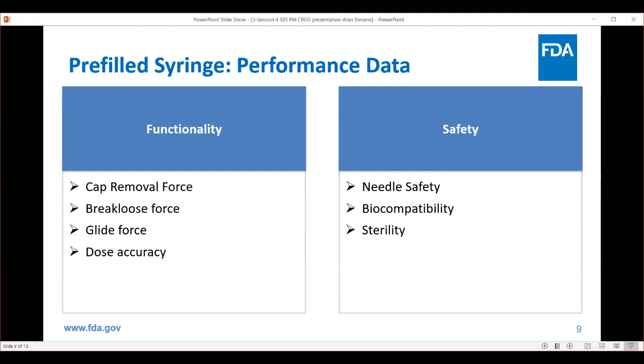So I'm just going to walk through the key performance criteria that we're looking at generally for syringes and injectors. So for functionality, we're looking for cap removal force, break loose force, glide force, and dose accuracy. For functionality, on the safety side, if there is a needle safety component, we're looking at the performance attributes of the needle safety device. That is a key issue.